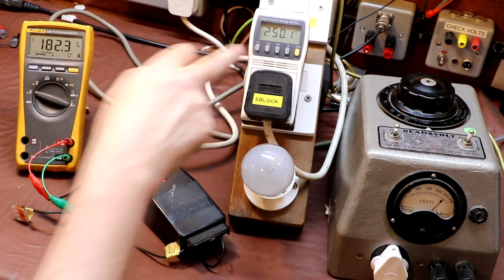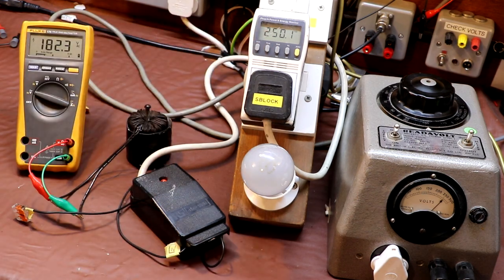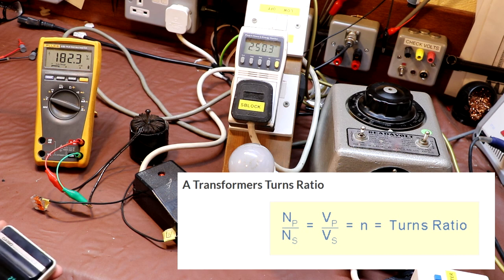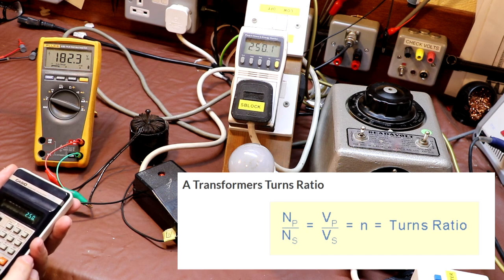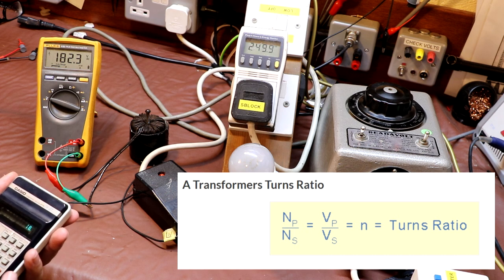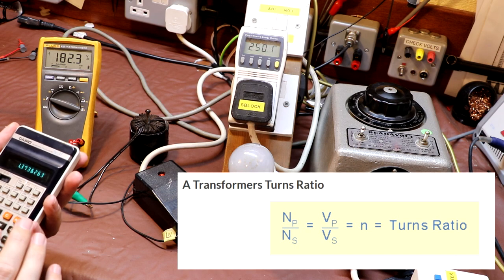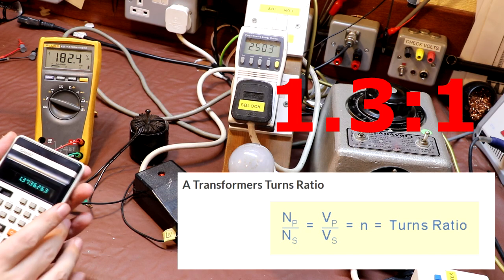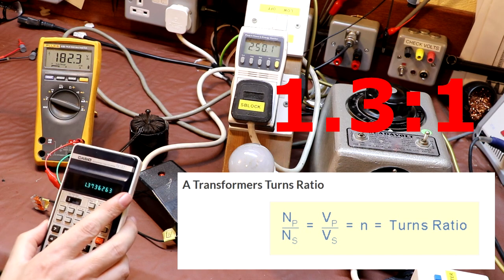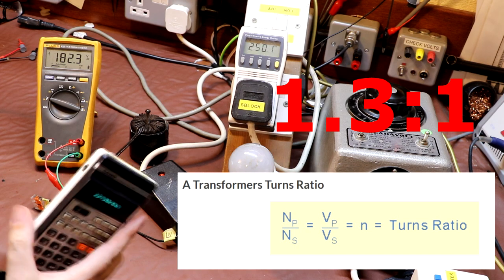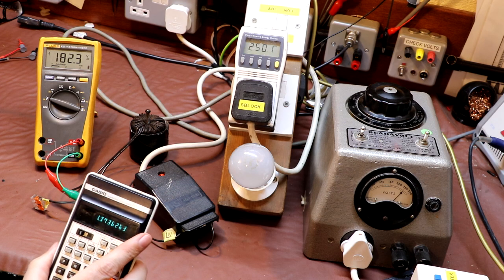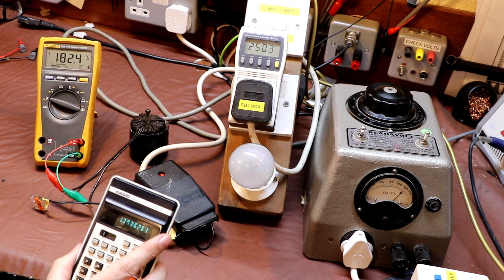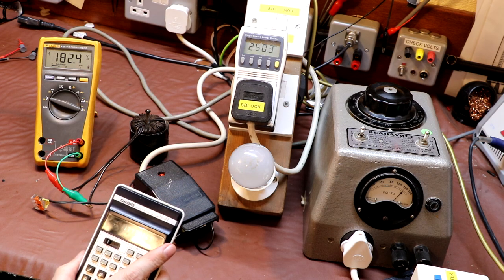With those two voltages, I can divide one by the other to give us the turns ratio. So all I've got to do is take 250 and divide that by 182, and that equals 1.3. So the turns ratio of this transformer is 1.3 to 1. For every one turn on the secondary, there's 1.3 turns on the primary.